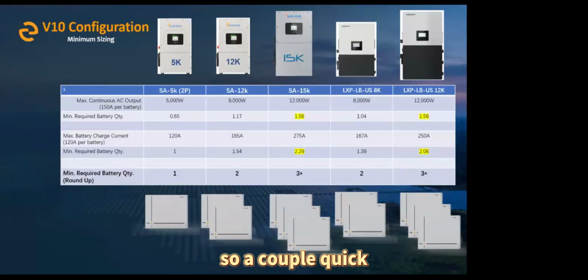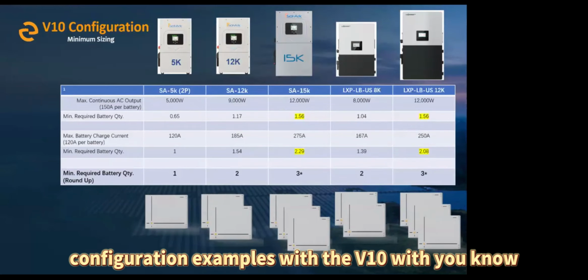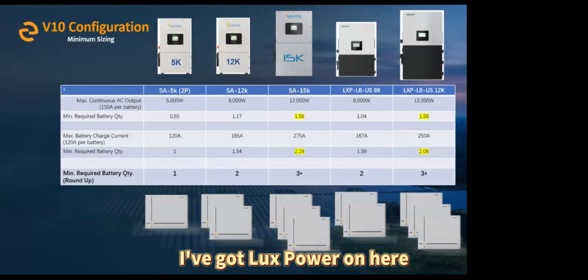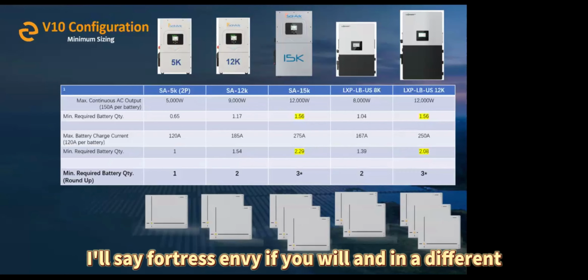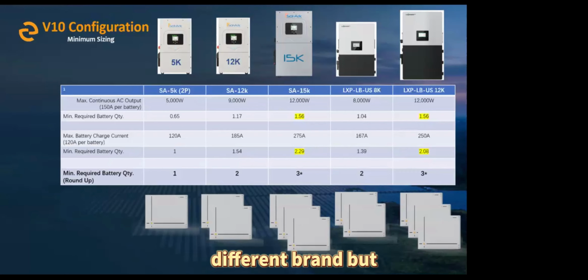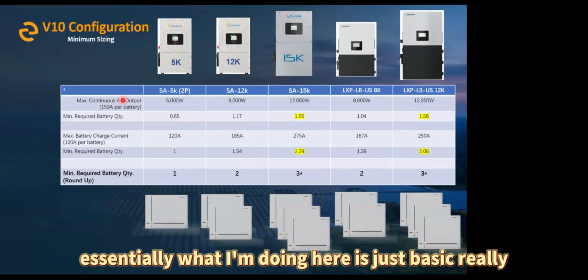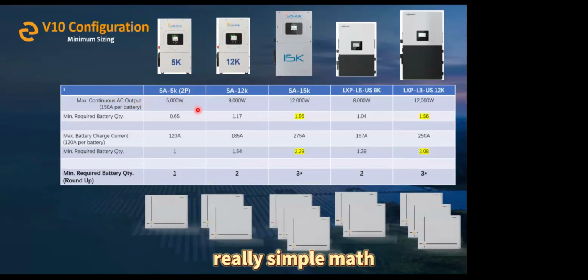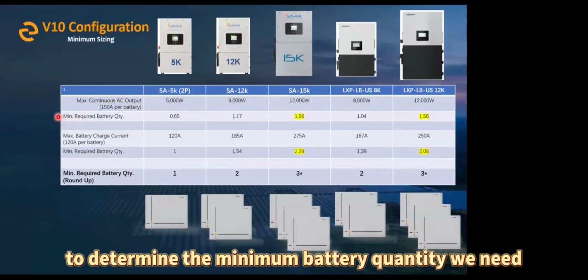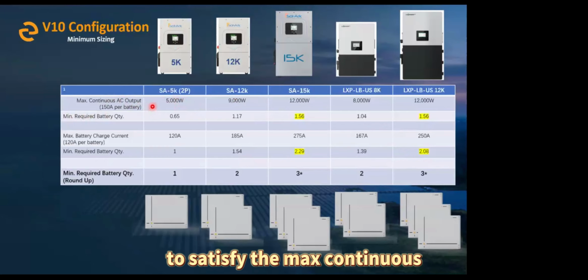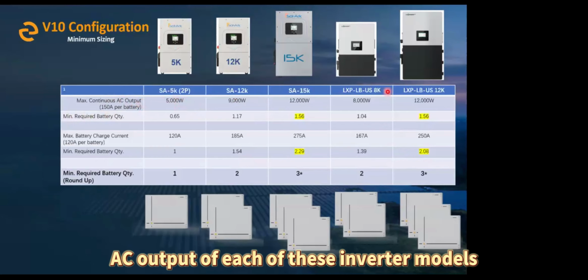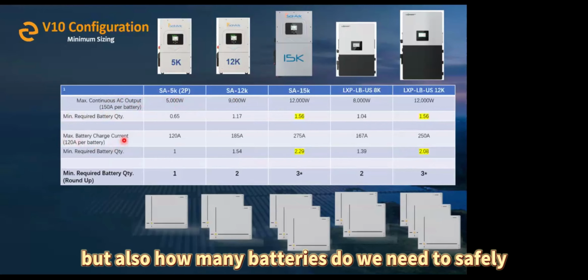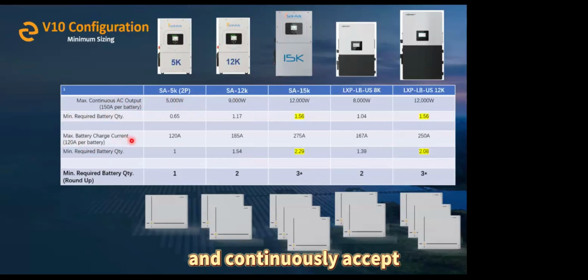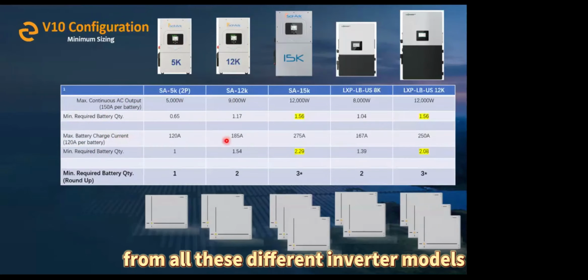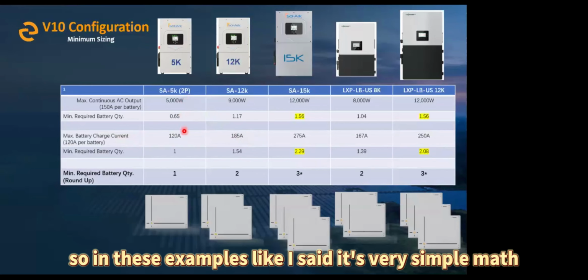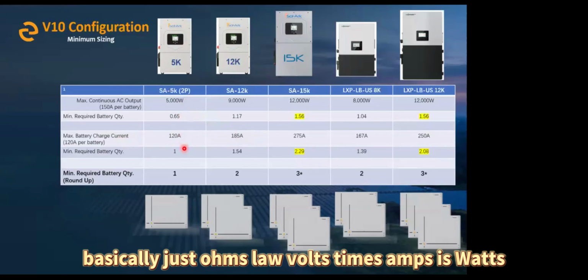So a couple quick configuration examples with the V10 with common inverter models, Sol-Ark, and I've got Lux Power on here, which is essentially Fortress Envy, if you will, in a different brand. But essentially what I'm doing here is just basic, really simple math to determine the minimum battery quantity we need to satisfy the max continuous AC output of each of these inverter models, but also how many batteries do we need to safely and continuously accept the max charging current from all these different inverter models. In these examples, it's very simple math, basically just Ohm's law - volts times amps is watts.